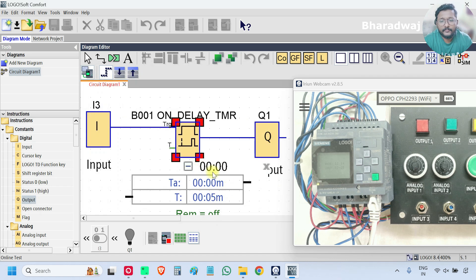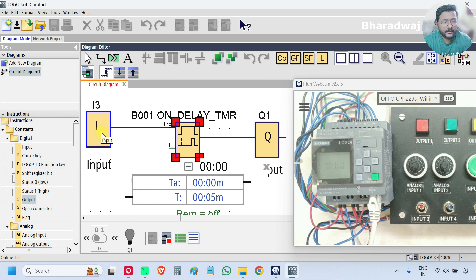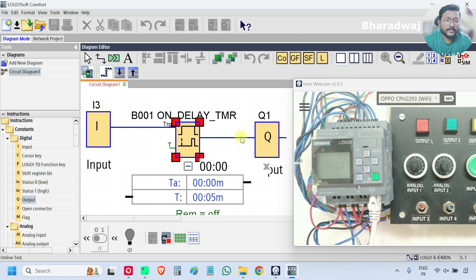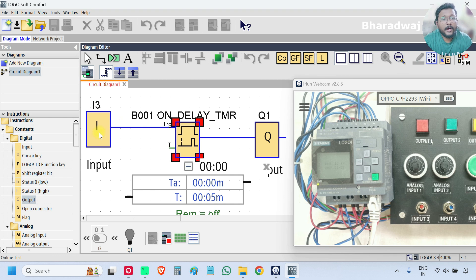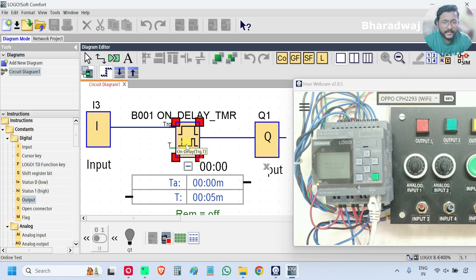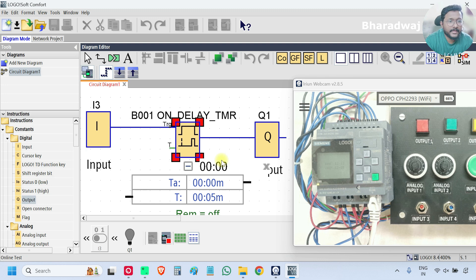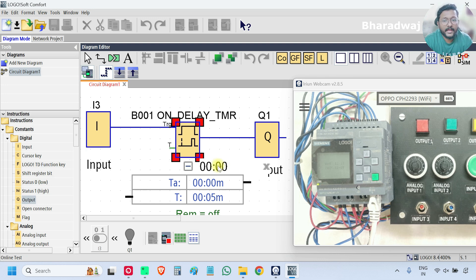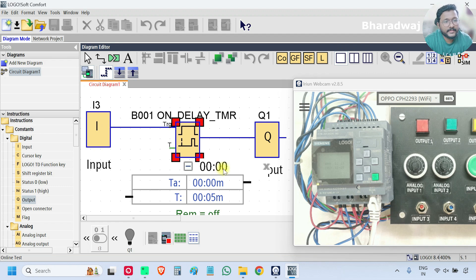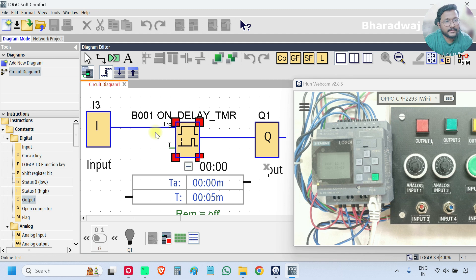So whenever the input is on for more than 5 seconds, then only the output will be on. That means the on status of the input is delaying for 5 seconds. Clear. On delay. On will be delayed for the specified amount of time. In this case, I entered 5 seconds. So the on status of the input will be delayed for 5 seconds, and the output will be on after 5 seconds only.